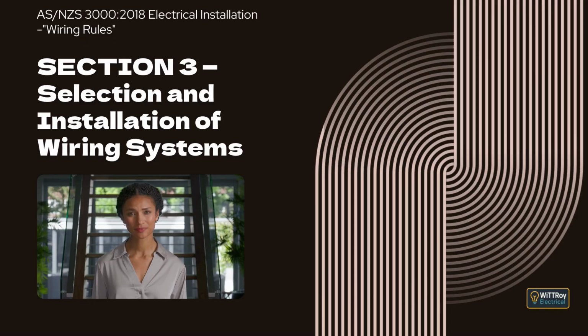Clause 3.7.2.3, Loosening of connections. This clause explains that connections must be made so that loosening is unlikely under normal service conditions, including vibration, material changes, and temperature variations. Clause 3.7.2.3.1, General. This clause reinforces that connections must remain secure throughout normal operation. Clause 3.7.2.3.2, Crimp joints, compression joints.